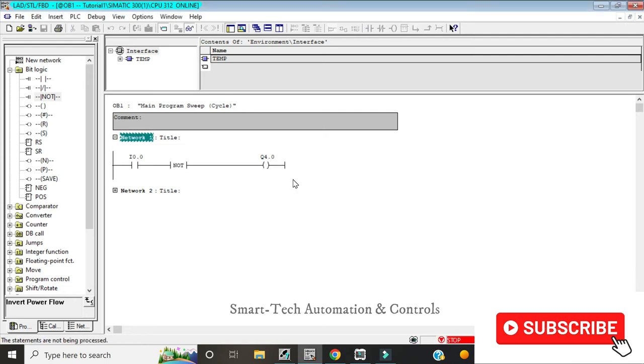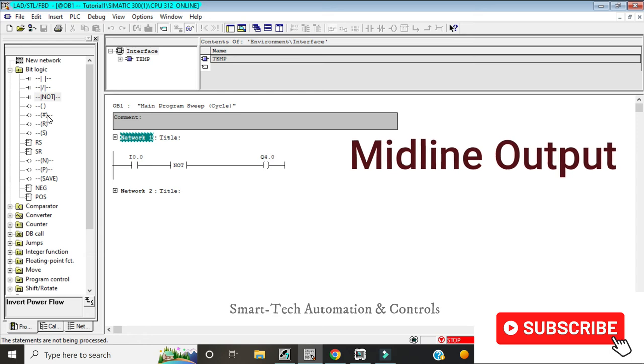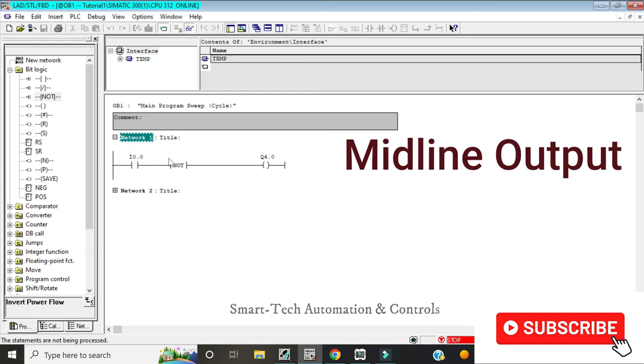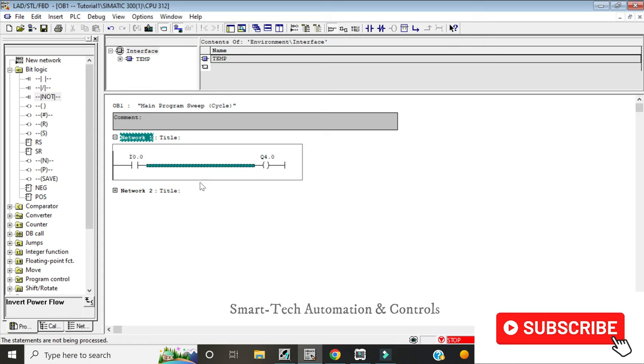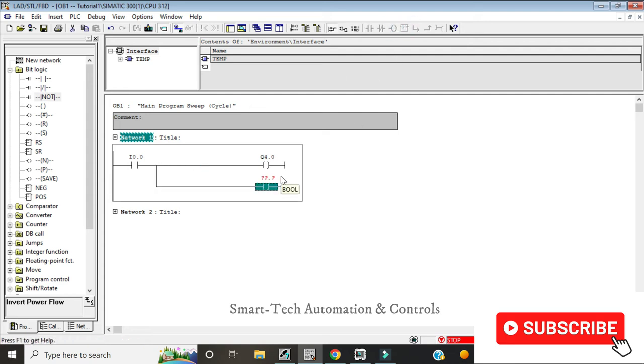We then have another bit logic known as midline output, this one, which is like a coil with a hash in the middle. You'll find that when you're doing ladder programming, it's not possible to arrange two outputs in series the way we had done with the normally open contact and the normally closed contact. For you to achieve two coils, you have to put in a junction, and then you have to arrange them like that. But now this bit logic, the midline output, can help you have two outputs which are arranged in series.